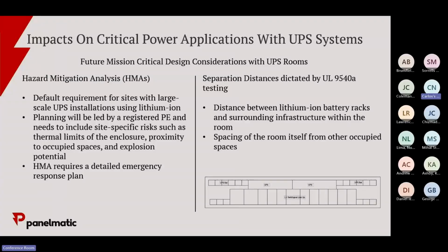So if you get into these kinds of applications - think of a UPS room or a switchgear enclosure, a modular enclosure going into a data center - you'll usually have switchgear, UPS, and batteries all slapped in one box. So ideally with this separation, those batteries have to be 3 feet away from the wall, just like electrical clearance requiring 4 feet in front of the gear - the batteries have to be separated, in their own space.